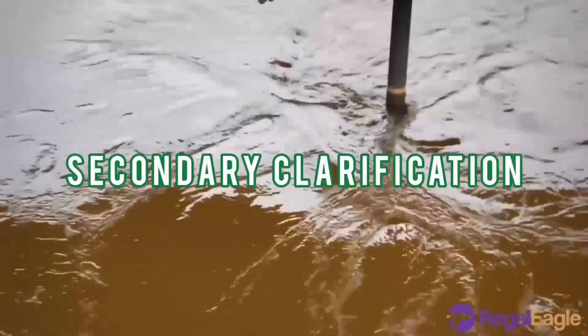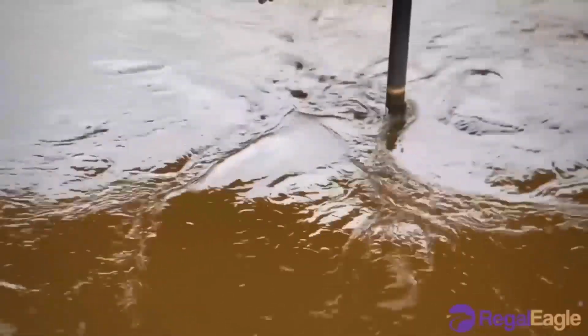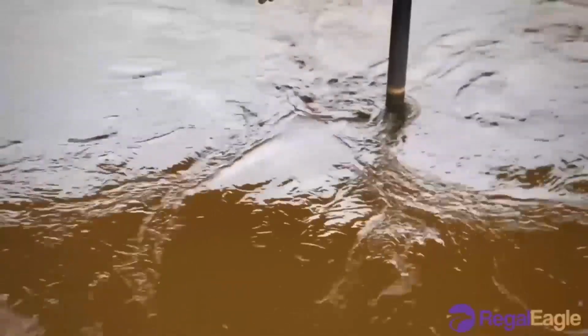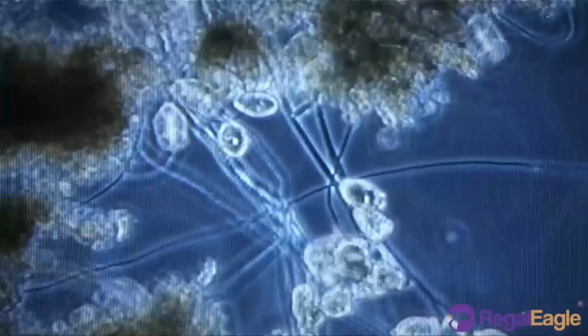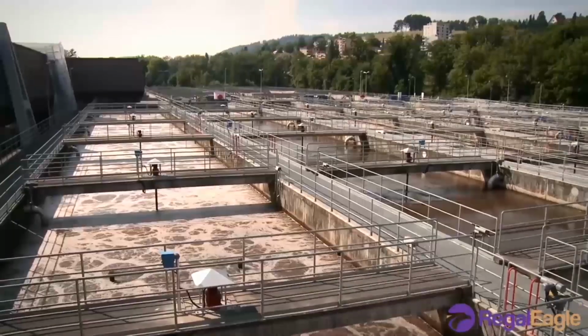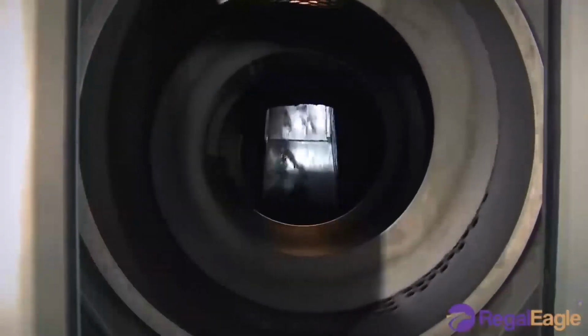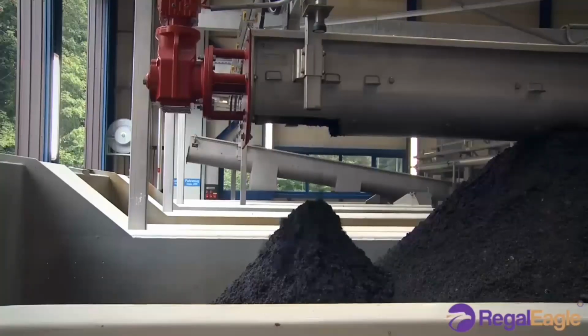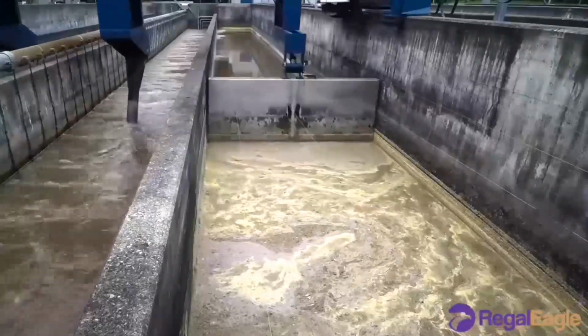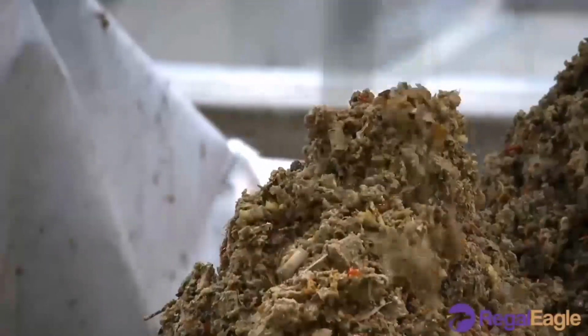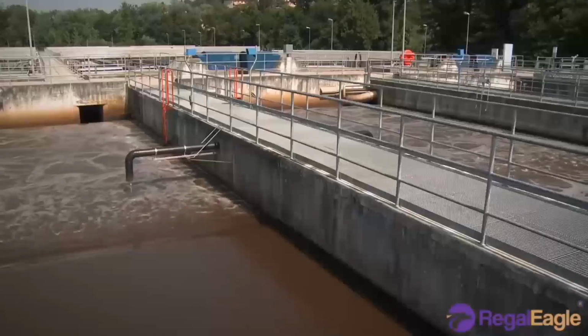Secondary clarification or aeration. During secondary clarification, we add air to aeration tanks to foster a healthy environment for oxygen-loving microorganisms that are naturally present in the sewage. These helpful microorganisms consume much of the organic materials in the wastewater, which yields heavy particles that can be removed more easily. Aerated wastewater then flows to final settling tanks where the heavier solids settle to the bottom. We remove most of this secondary sludge and combine it with the primary sludge for thickening and digestion.